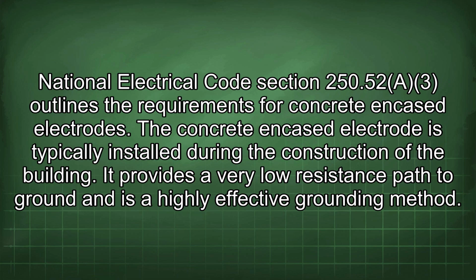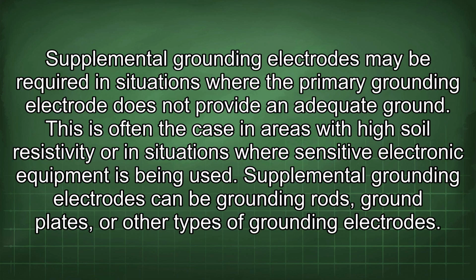The concrete encased electrode is typically installed during the construction of the building. It provides a very low resistance path to ground and is a highly effective grounding method. Supplemental grounding electrodes may be required in situations where the primary grounding electrode does not provide an adequate ground.